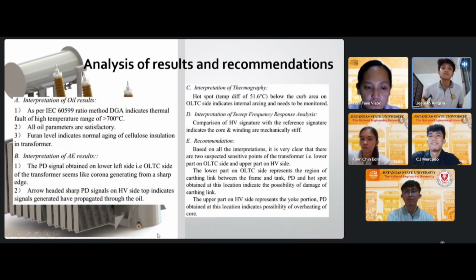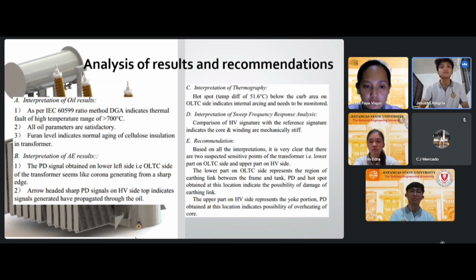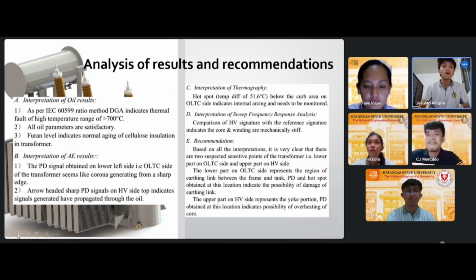As per the analysis of the problems in this study, the analysis of results and recommendations were also done. First, the interpretation of oil results. As per the IEC 60599 ratio method of dissolved gas analysis, it indicates a thermal fault of high temperature range, greater than 700 degrees Celsius. Second, all oil parameters are satisfactory. The furan level indicates normal aging of cellulose insulation.